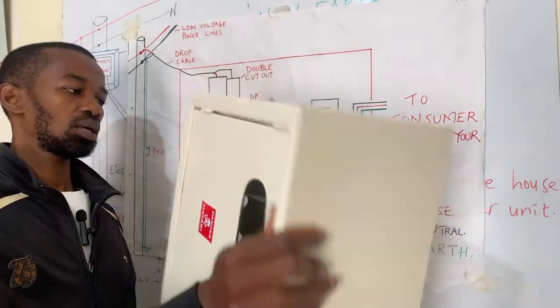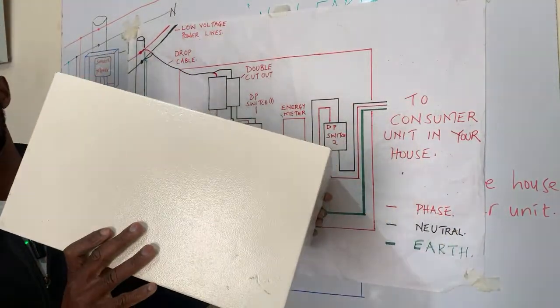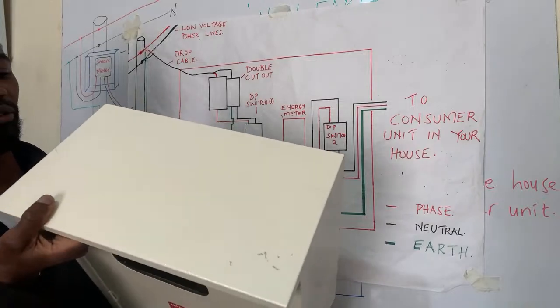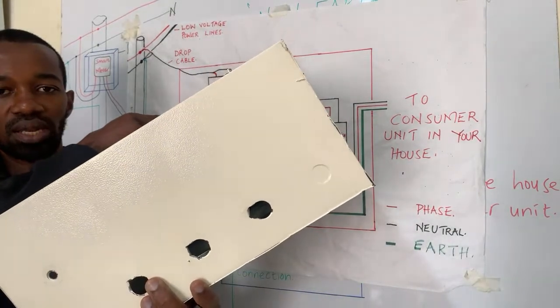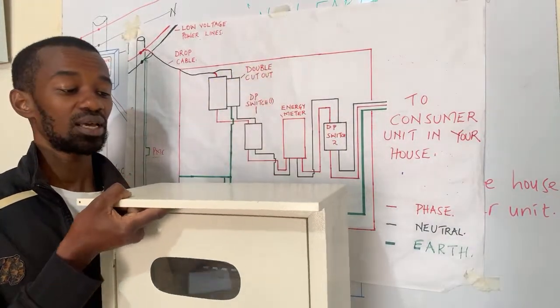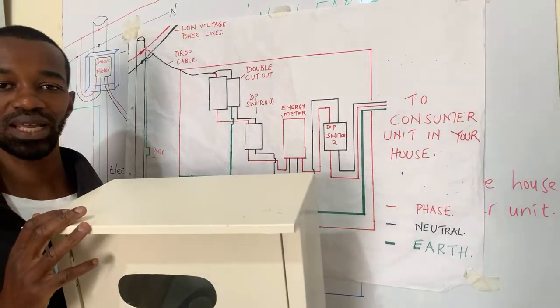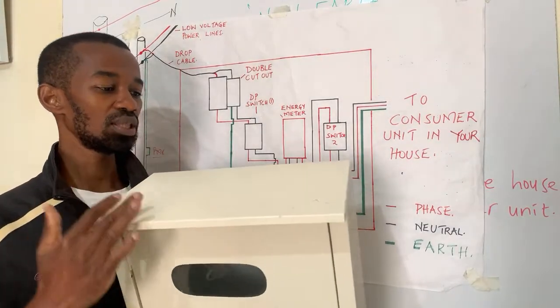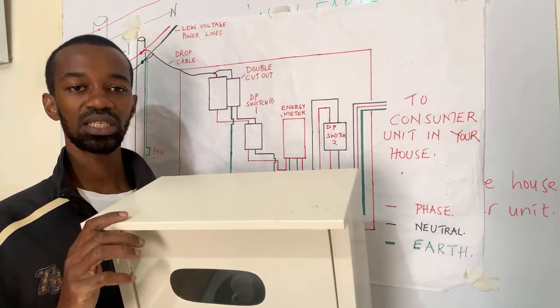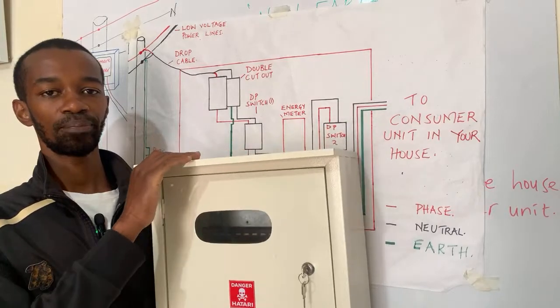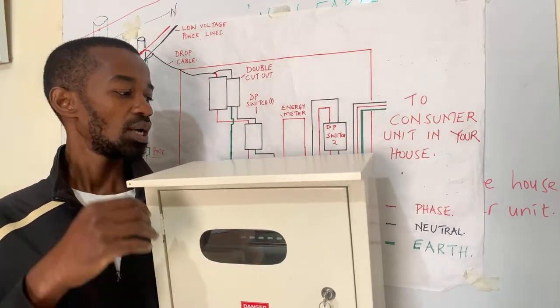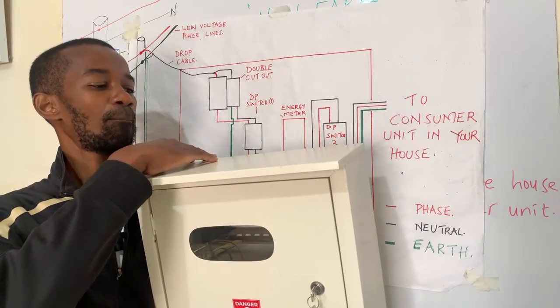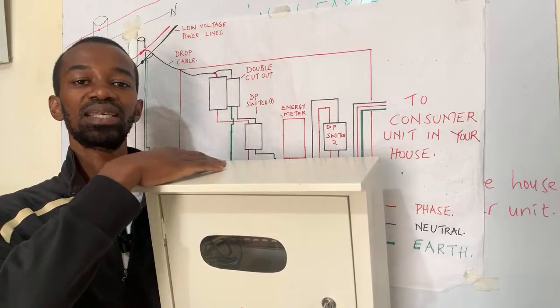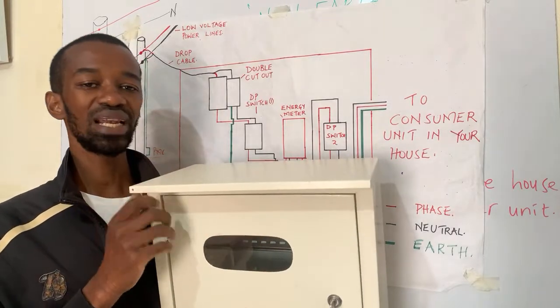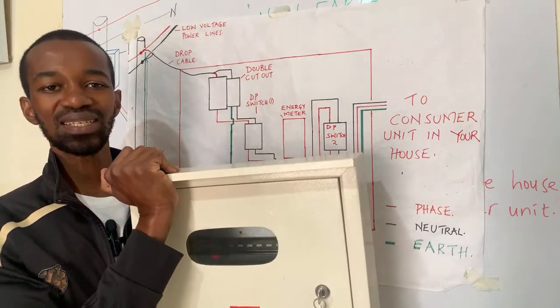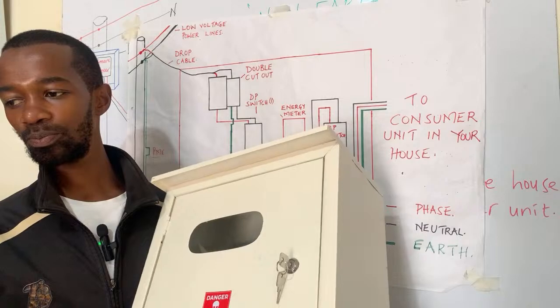At this bottom section of our meter box, we have certain provisions that you don't see at the top section, so that you can prevent cases of water leakages into the meter box. The meter box is usually installed outside the house, so if there is heavy rainfall and the pipes or conduits are connected here, it can be susceptible to water leakages. Once water gets into the meter box, that is a recipe for disaster.